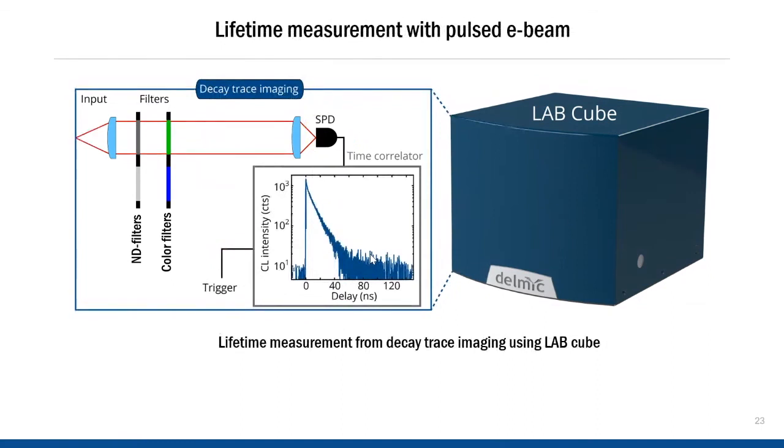The second method for lifetime measurement is called time correlated single photon counting. It requires a pulsed electron microscope. This is also set up using the lab cube, as I described earlier for the G2 imaging, but the difference is that you only use one single photon detector together with this time correlator. Now, since this method requires electron pulses and electrons repel each other, you can only use low currents of the order of 10 picoamps in this mode. Higher currents would create undesired space charge effects. So this mode is also quite slow, and you need to acquire often for several hours.